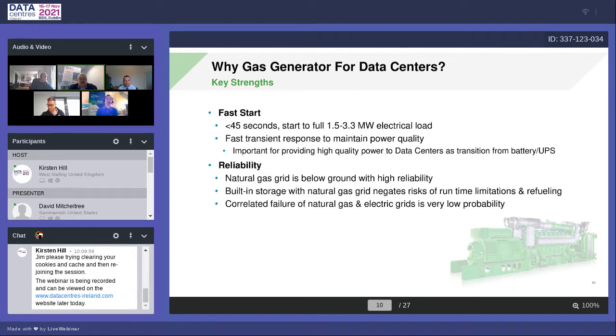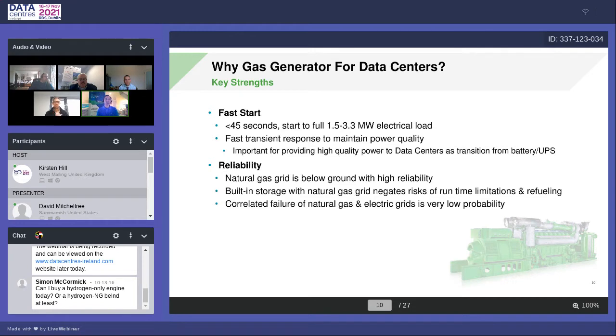Fast start was the big technological step forward, the ability to take on full load up to 3 megawatts in under 45 seconds. We've tested it down to 30 seconds, but we guarantee 45 to be prudent. You could do that in a linear ramp, or with stepped increments, which is the prudent way, as you're taking load off the UPS, your short-term energy insurance policy in the form of batteries, providing nice frequency, voltage, and overall transients, high quality power back into the data center.